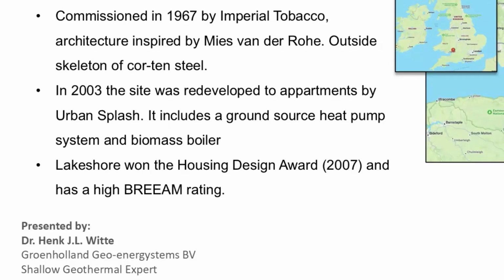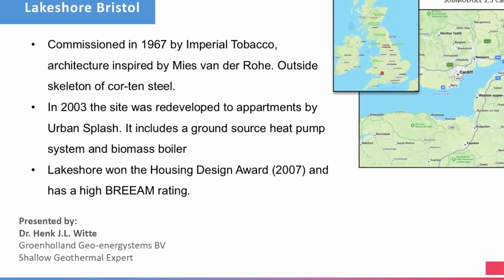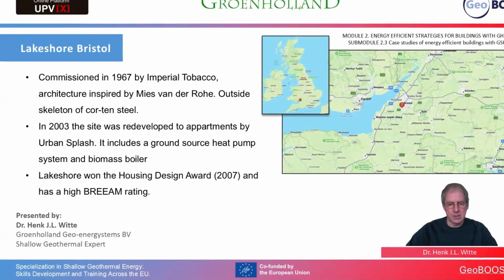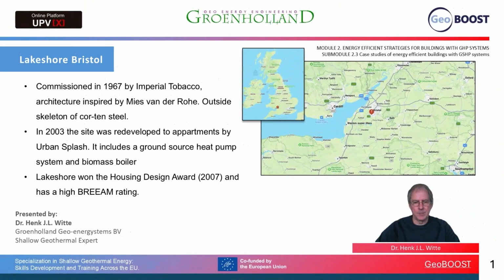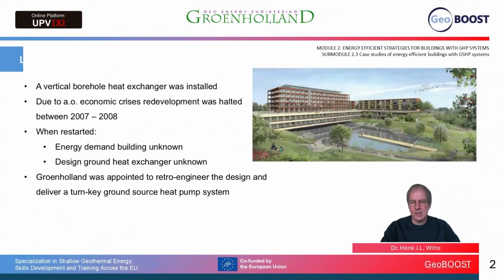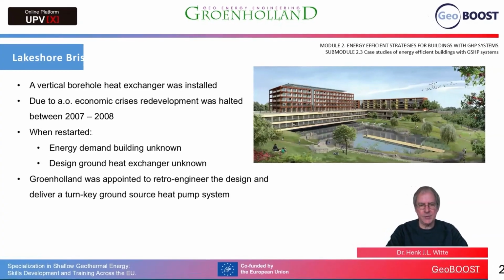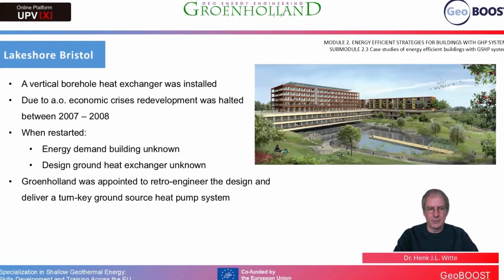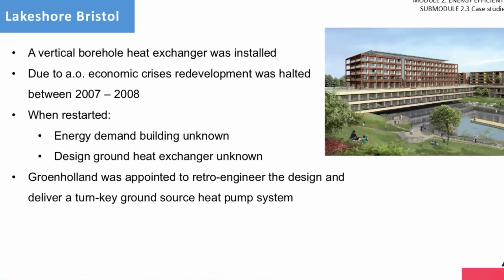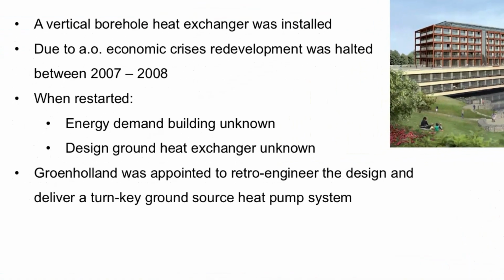It won the Housing Design Award in 2007 and has a very high BREEAM rating because it's a very energy efficient building. So on the right here, we can see an artist impression of the actual site. It already had a vertical borehole heat exchanger installed, but due to, amongst others, the economic crisis, redevelopment was halted between 2007 and 2008. When it was restarted by Urban Splash, the energy demand of the building was unknown, and also the design of the ground heat exchanger that was installed was unknown.